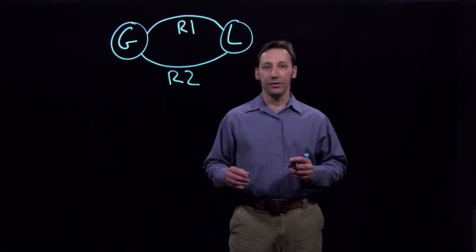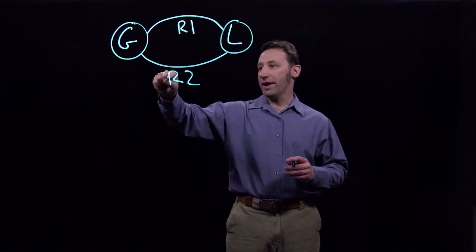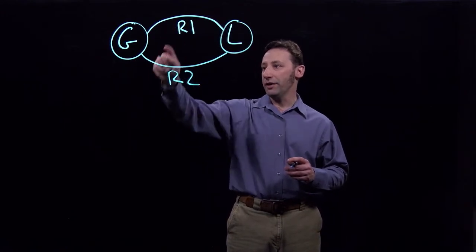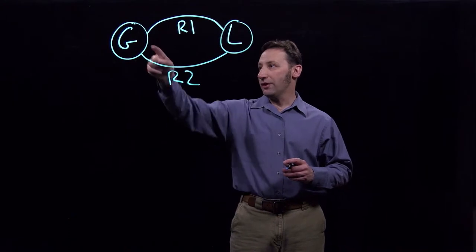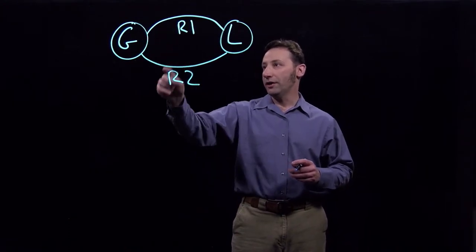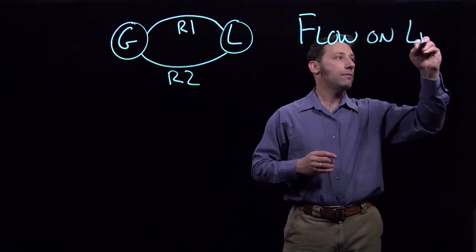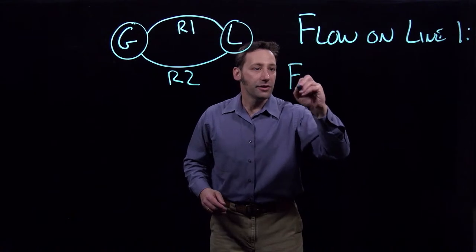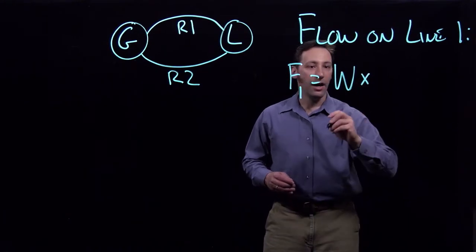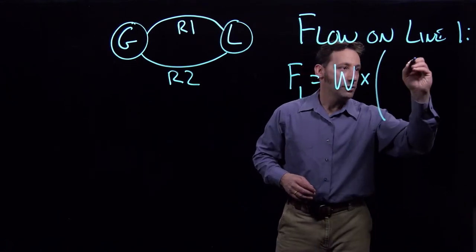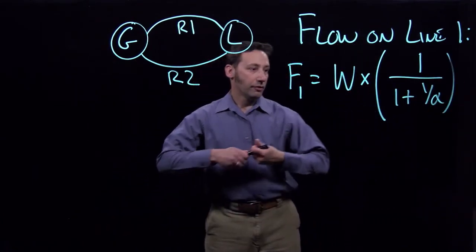To use the distribution factors to calculate power flows, we realize that the distribution factors simply tell us the proportion of power that's going to flow on each of these two lines. The total amount flowing on each line is the amount produced at the generator times the distribution factor on each line. So the flow on line one is going to be equal to the power produced at the generator times the distribution factor on line one, which is one over one plus one over alpha.